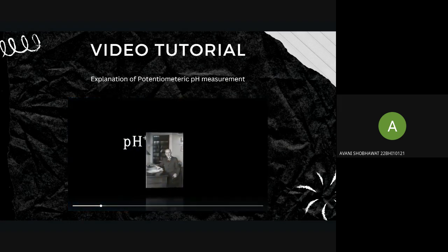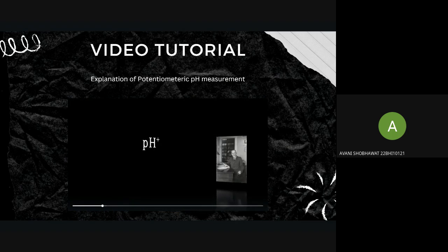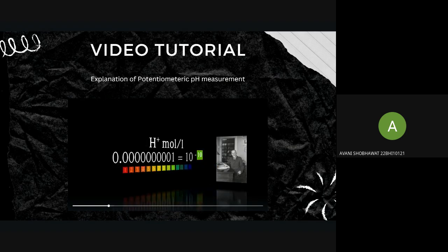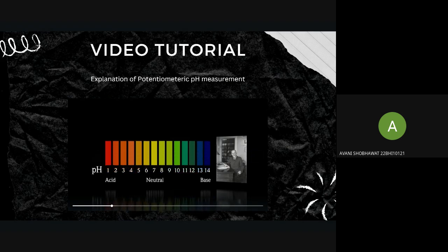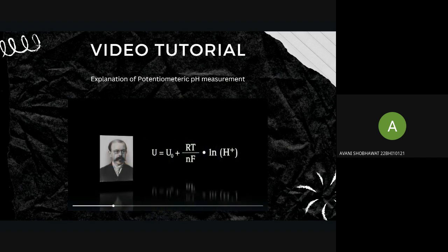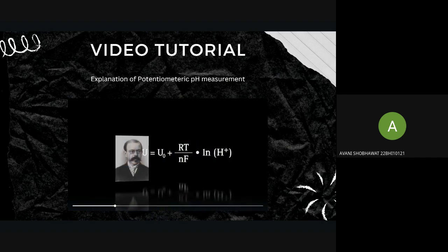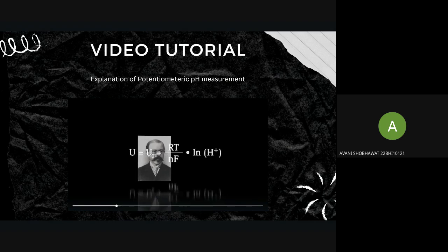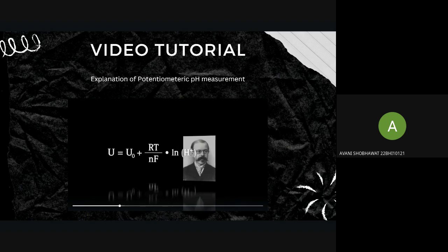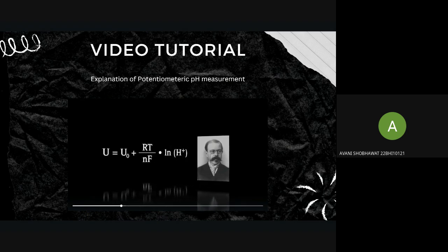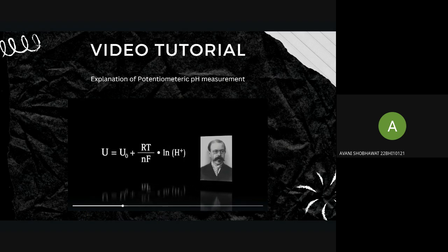The principle can be traced back to 1909, when the Danish chemist Søren Sørensen introduced the so-called hydrogen ion exponent pH+, to describe the concentration of hydrogen ions in a solution. This was the basis for the development of the conventional pH scale. In 1889, Walter Nernst formulated the Nernst equation that for the first time related electrical voltage to ion concentration. The Nernst equation derived for pH is the physical basis for pH measurement according to the potentiometric principle.